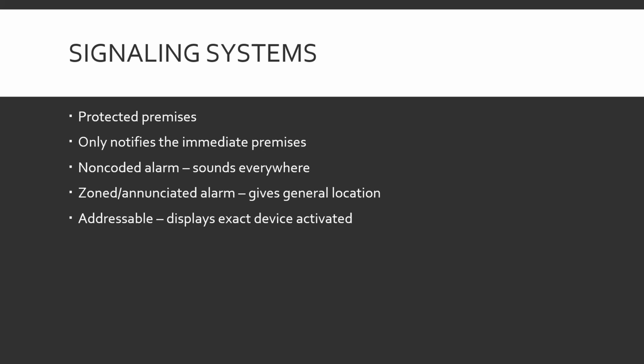A couple of different terms to remember. These can be in any of the upcoming systems in different amounts, depending on how the building is, how big it is, what they want to pay for. Non-coded alarm: those sound everywhere. I'm going to use a school as an example because it's easy. Someone pulls the fire alarm in the gymnasium. The alarm goes off everywhere, all the hallways, the library, all that kind of stuff, and it's not really specific. The fire department shows up, and we don't know if it's a smoke detector or someone pulled an alarm. We have to search the whole building and find what was tripped.